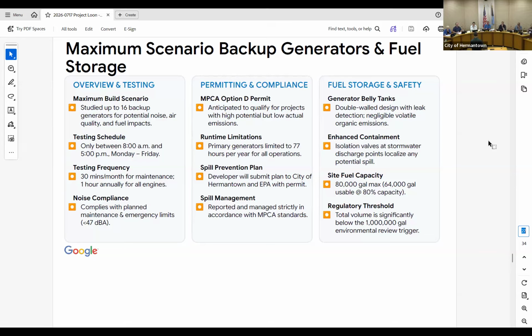As far as testing of the generators, that testing would typically be run in pairs or in tandem, with two generators running for sometimes 30 to 60 minutes at a time. That testing would only occur between 8 a.m. and 5 p.m., Monday through Friday. During those planned maintenance activities or whenever the generators are running, the project would need to remain in compliance with the 47 dBA nighttime standard.